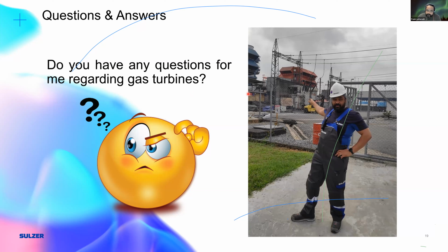Quickly, for overspeed you have two ways of doing it. You either do a live overspeed test, where you physically accelerate the rotor to the limit and trip the unit - that's what Alstom turbines typically do, or used to do. Siemens instead simulates a lower frequency and activates the individual channels. Both actually work the same way in terms of issuing the trip signal during a startup, and there's really no advantage or disadvantage.